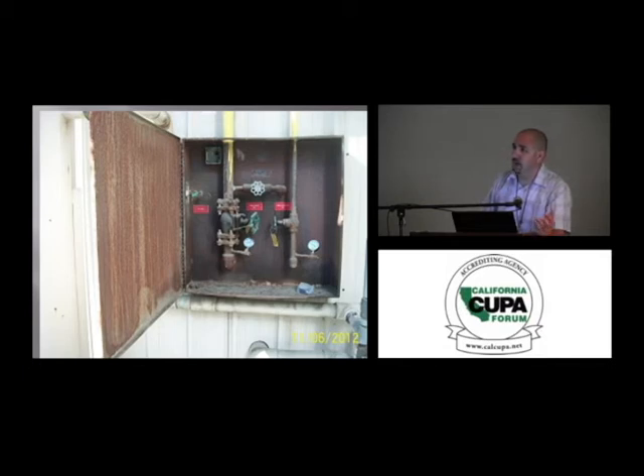And I could tell the cap is different age-wise from the pipe. So at some point that was capped off. So that's one important thing to keep an eye out, to make sure that high side to low side equalizer is connected. Yeah, in the old days, up until the code just changed, you had to have a manual high to low, okay?